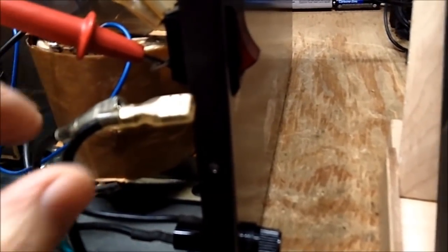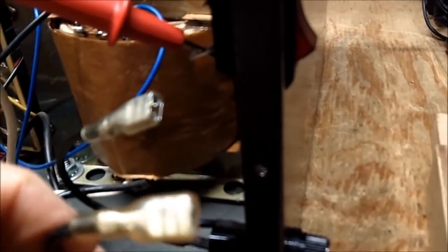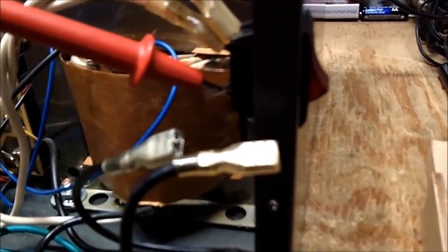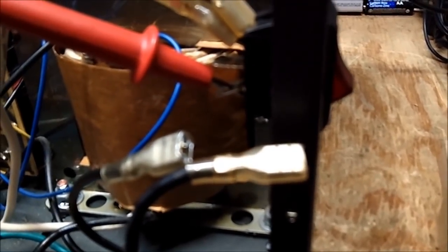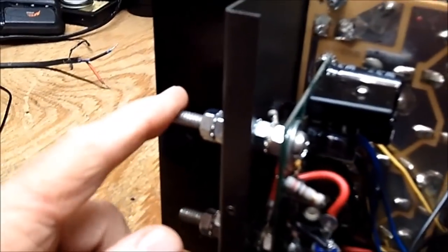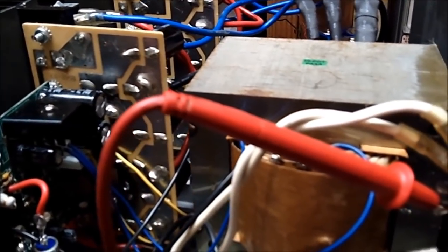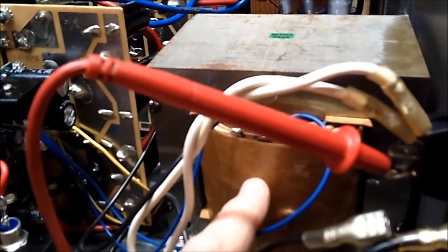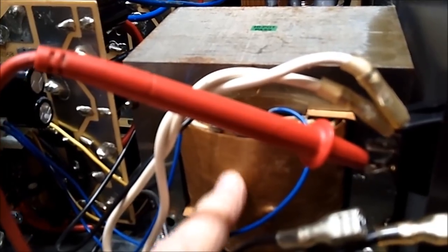There is still a 20 amp fuse in here, it's supposed to be 15. But if I run this through my dim bulb, which will probably light up the dim bulb quite bright, because even without a load out here, there's going to be a surge. And this transformer has such a low impedance on the input...